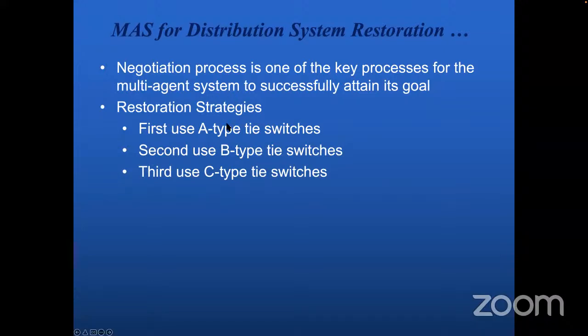First, we want to take power from our own substation, our own transformer, that's the A type switch. If A type switch cannot do it, then we want to try the B type switch, because it's the same substation. And if A and B fail or are not available, then we can tap into the C type switches and take power from another substation.